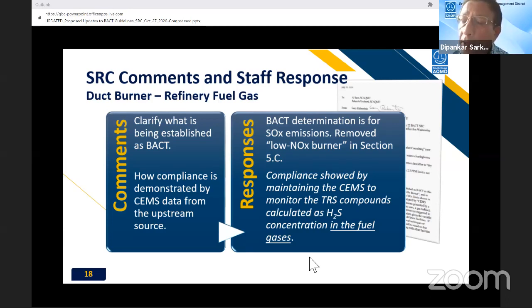There are two ways of measuring stack flow rate, David, as you know. One is to measure fuel flow rate, and knowing the composition of the fuel, you can convert that into stack flow by combustion. The other is to measure stack flow directly in the stack using ultrasonic or a Pitot tube. So this fuel flow meter is also, you're correct, part of the CEMS along with the TRS monitor. And the fuel meter is tied to RATAs—they have to do RATAs every so often, once every 6 months or once every year.